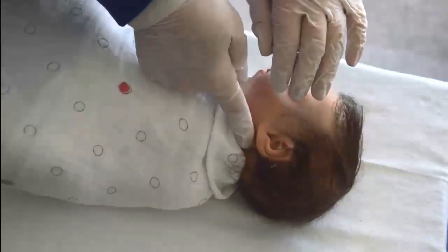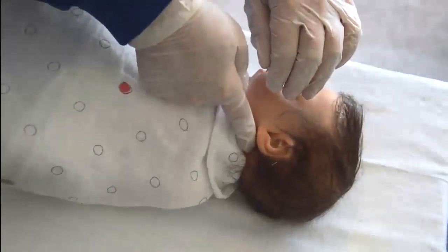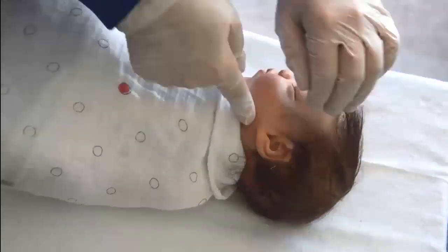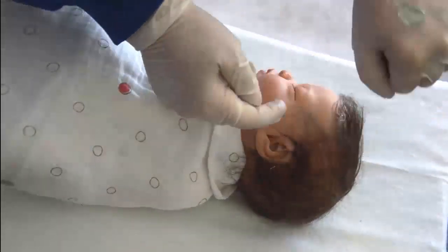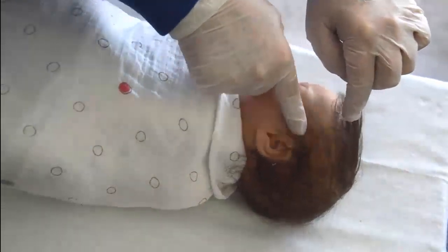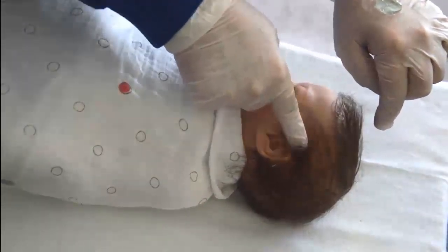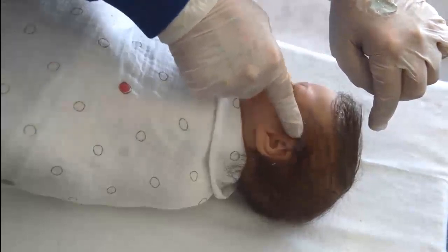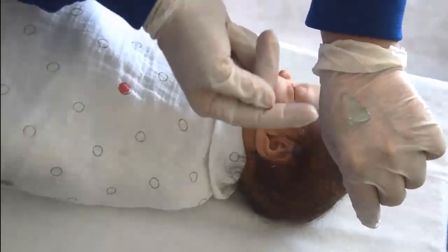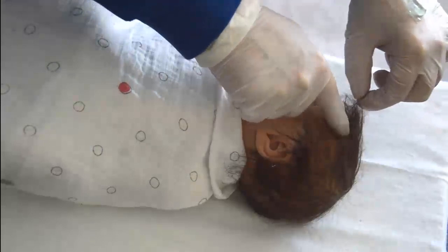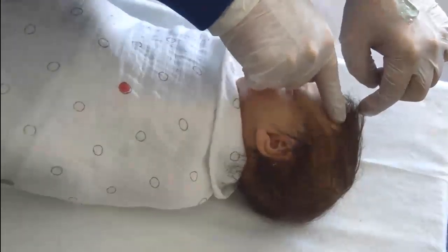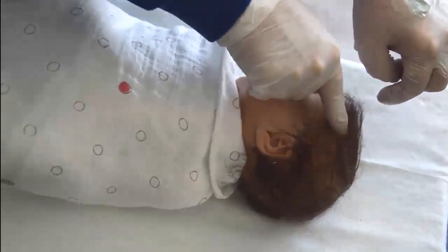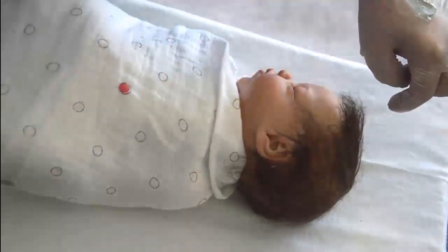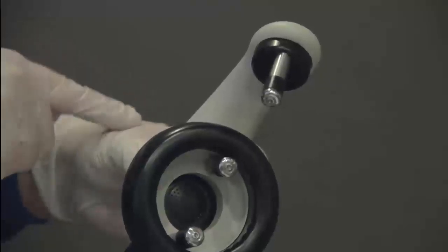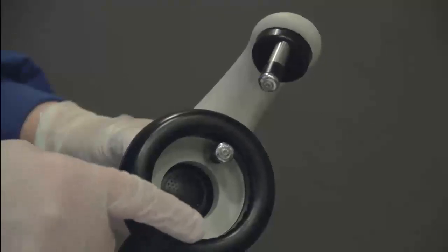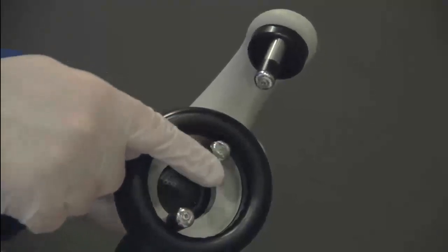Using an additional drop of electrode gel, rub the skin at the mastoid location 15 to 20 times in a straight line from the back to the front. Repeat this procedure at the 2 other electrode locations. Keep the gel at the 3 areas parallel to one another so that there's no chance that the gel from one location will contact the gel at another electrode site. Avoid using too much gel and avoid rubbing the gel in circles. Apply a small amount of electrode gel, just enough to wet the top of the electrode, onto each of the electrodes.